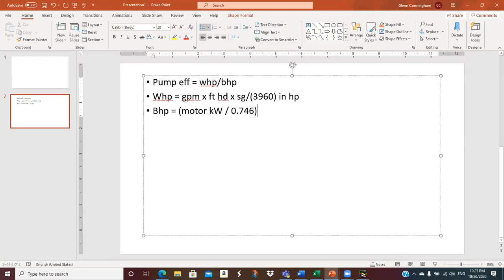Okay. And so, okay, so that's the power into the motor. Okay. But part of that is eaten up by the motor efficiency times, and these efficiencies are in fractions, and times any drive efficiency, if any. Okay? So the assumption in PSAT is that you're going to measure that motor kW.